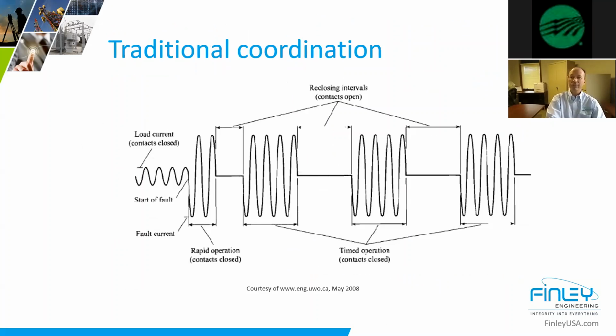Also, when you look at a traditional coordination, very typical, you've got a load current, and when we have a fault event, we're having some series of either fast operation to clear the temporary faults or the slow operations to get the rest and try to clear.